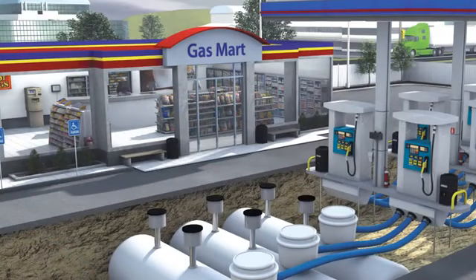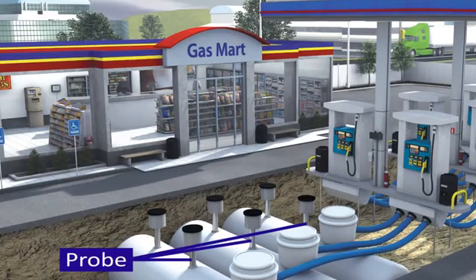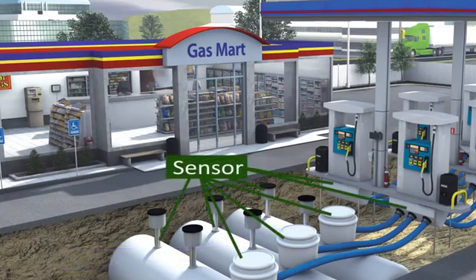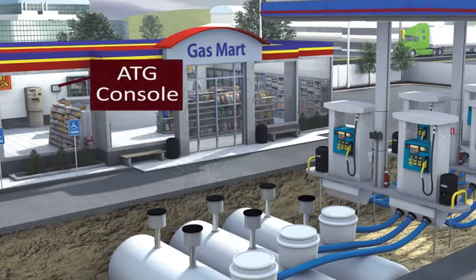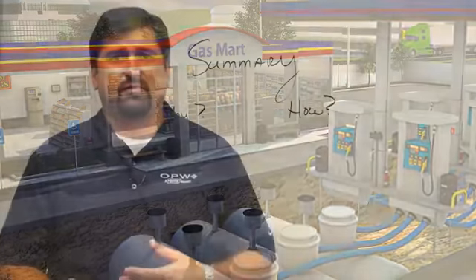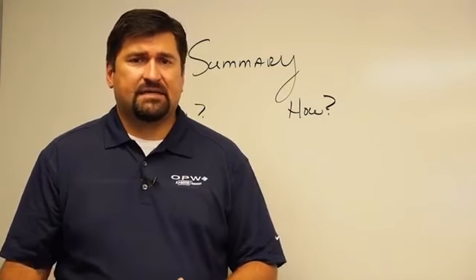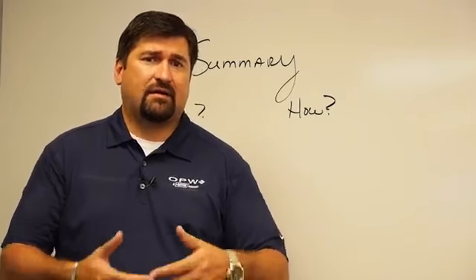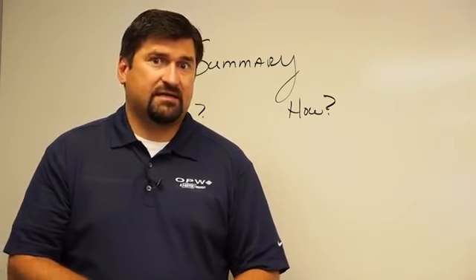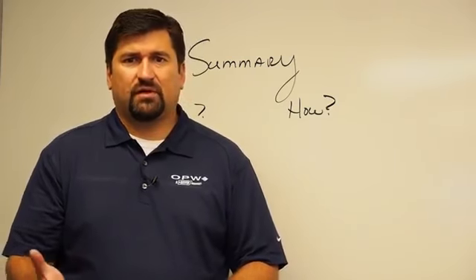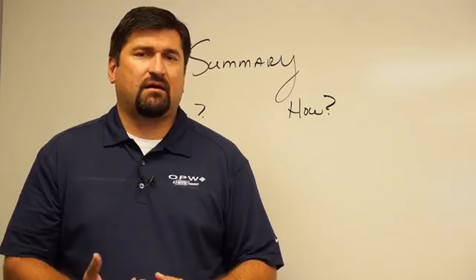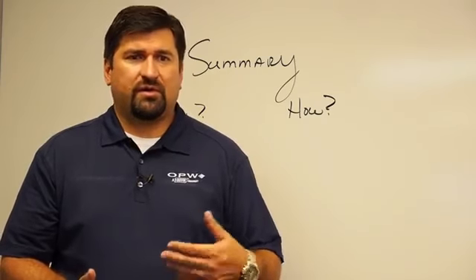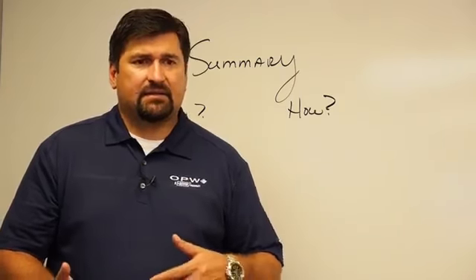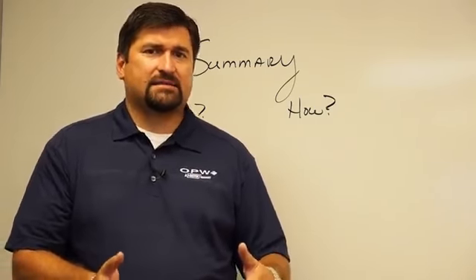The how is the easy part. It's basically just installing a probe in the tank and sensors either in the annular, the STP sump, the dispenser pan sensors, a monitoring well, a transition sump. It's basically just installing an ATG at their facility and then setting it up to monitor it and setting the thresholds that you want it to alarm. And then once you have it set, basically just telling them how do you want it to communicate out to the outside world, whether it be an email, a fax, or a text message. Do you want it to send out an email on fuel in an STP sump? Do you want it to send it out to the delivery carrier on a low product alarm? Do you want to know when you get water in the tank? People start looking at the how as the hard part, when that is the actual easy part.